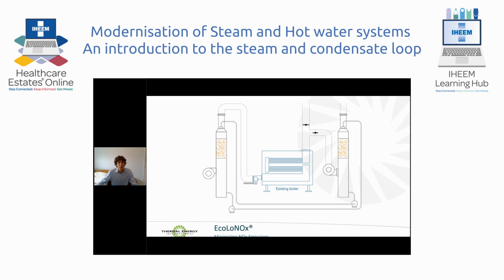Instead, it humidifies the combustion air through a preheating evaporator and completely saturates it. This additional water in the combustion air increases the specific heat capacity of the combustion gases, significantly lowering the flame temperature and achieving NOx reduction. As we do this, we're also preheating the combustion air, meaning that heating doesn't have to be completed by the burner, increasing the efficiency of the overall system by typically 3%.